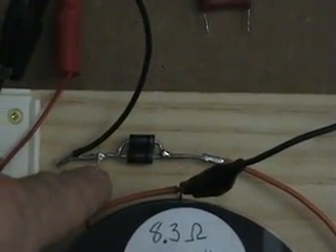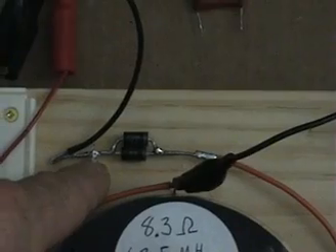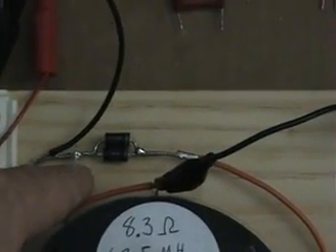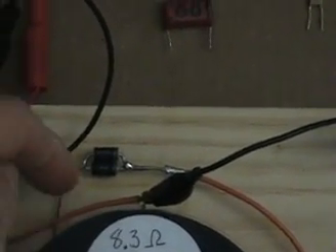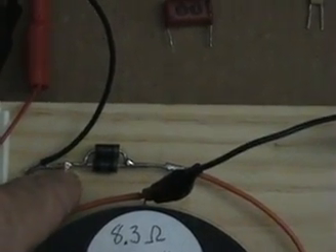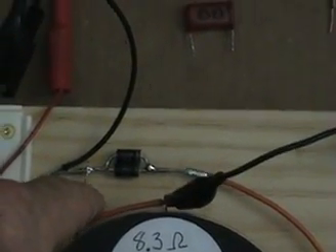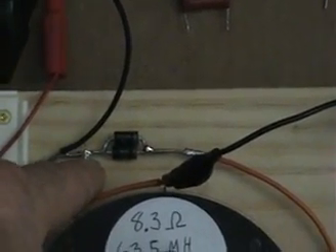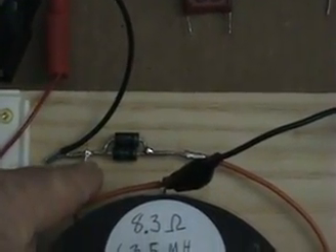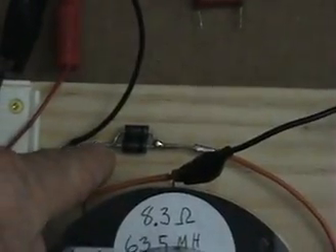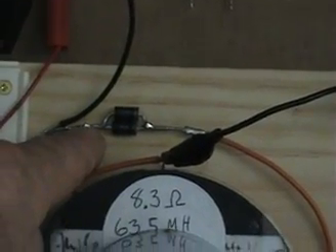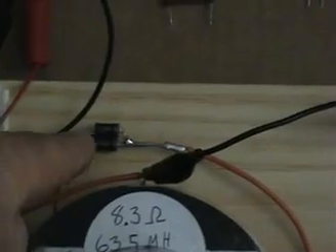But if we have a switch off of the coil that was energized, what's going to happen is the coil will kick back, which is known, some use the term back EMF, or it's also known as an inductive kick back, or it's also known as fly back. Anyways, the coil kicks back the energy that was stored in there, but going the opposite way that it was going in.